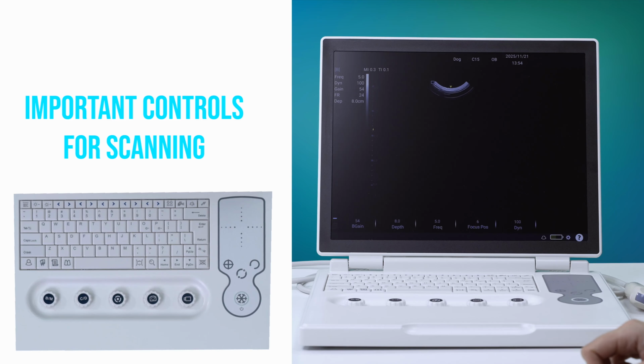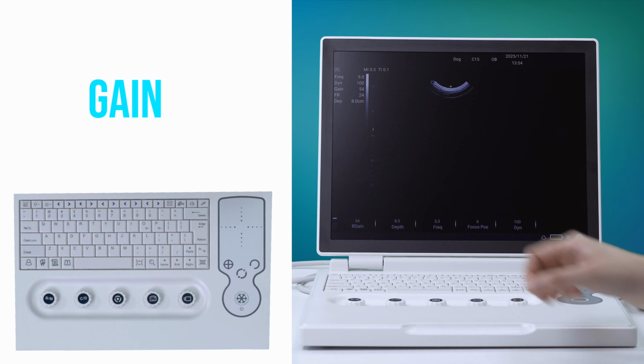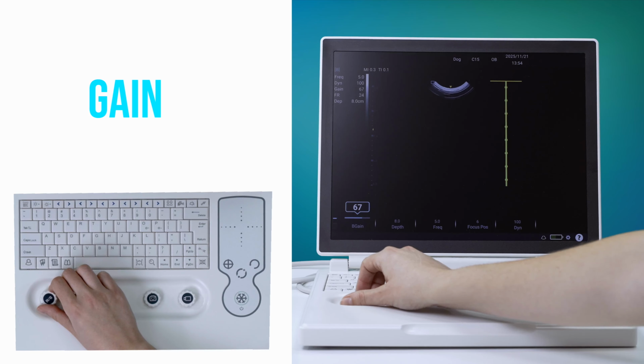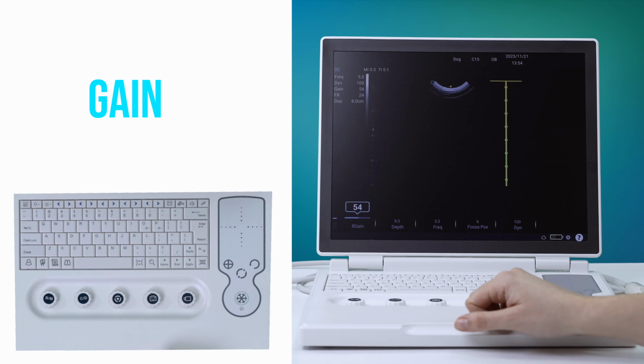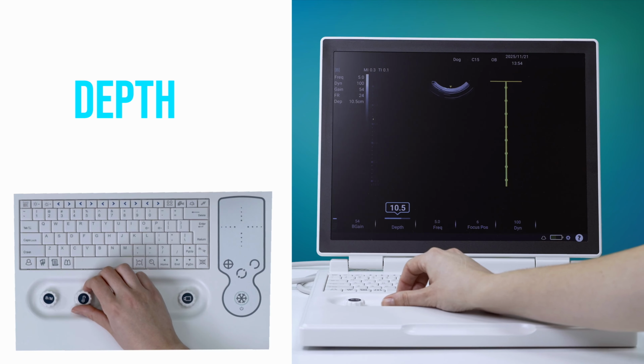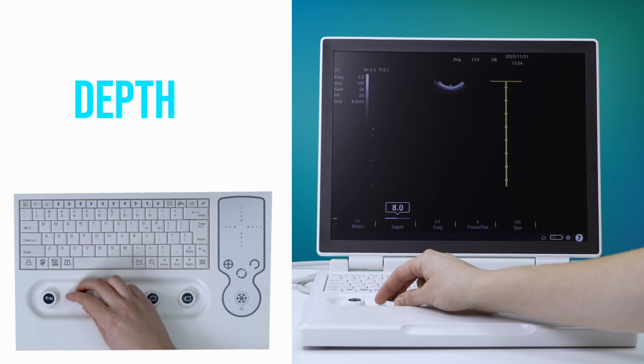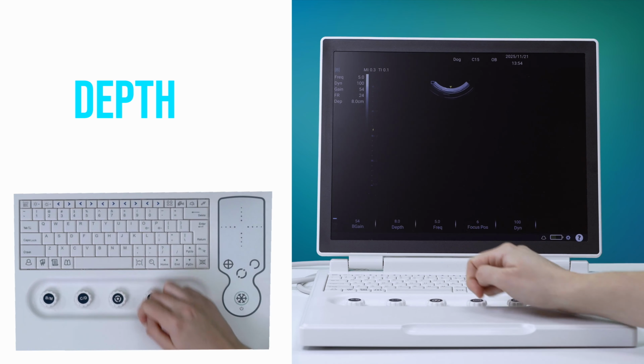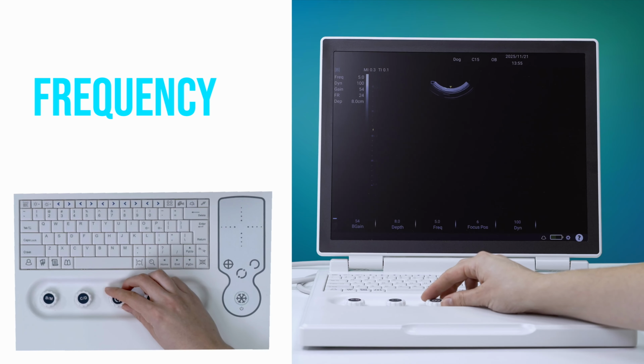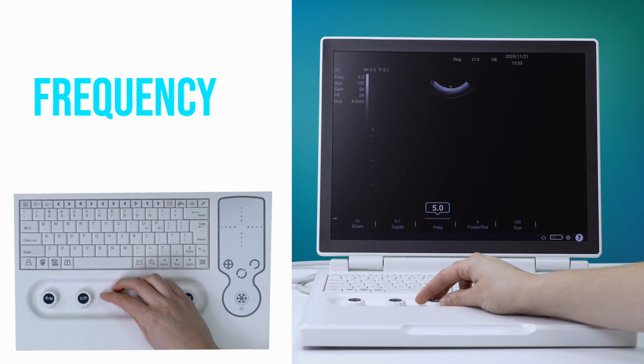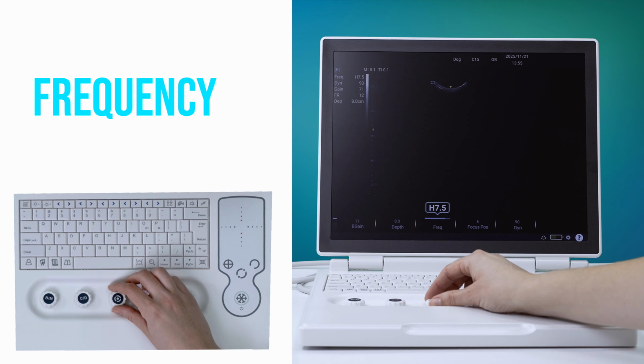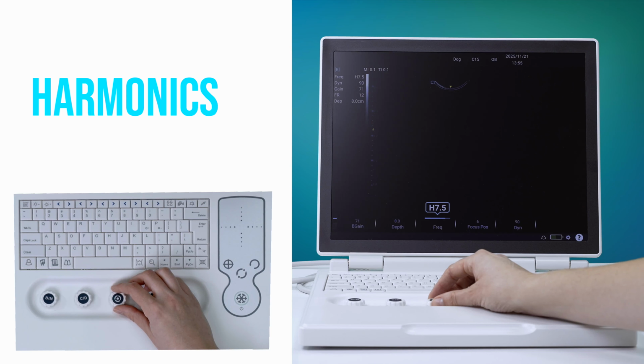The most important controls for scanning are gain, which is how bright or dark your image is, which you adjust here. Depth, which you adjust with this knob here. You can see these are in line with the words on your screen. Frequency, lower usually for larger animals, higher for smaller animals. You also have harmonics on this machine, so you can go up to the highest frequency in your fundamental frequency range. You can jump up to your harmonics if you want to.